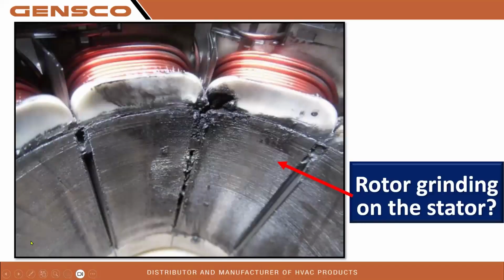Now this is an example of a slot short due to mechanical wear. If you look at the inside of the stator, you will see that the bottom looks fairly smooth, and as we get close to the top, it's grooved. The rotor has been rubbing on this. It filled the gap with metallic debris, and there was an electrical bridge made. And you can see the burn marks there.